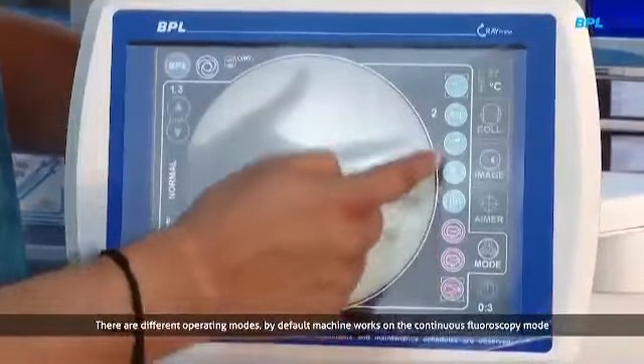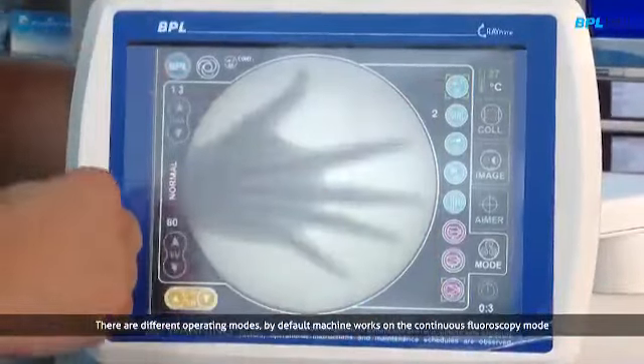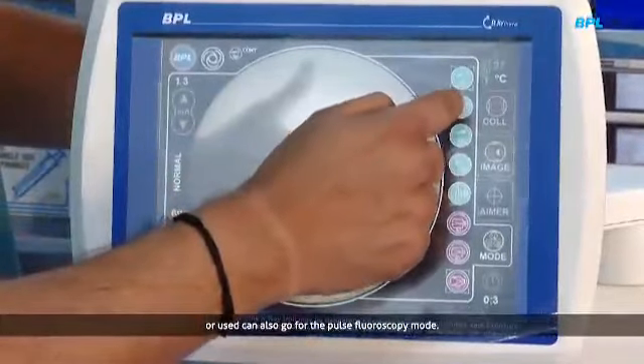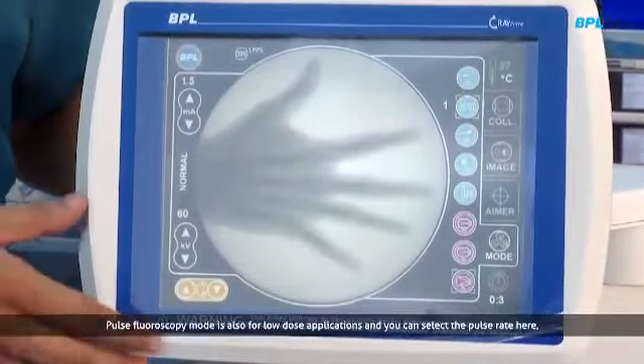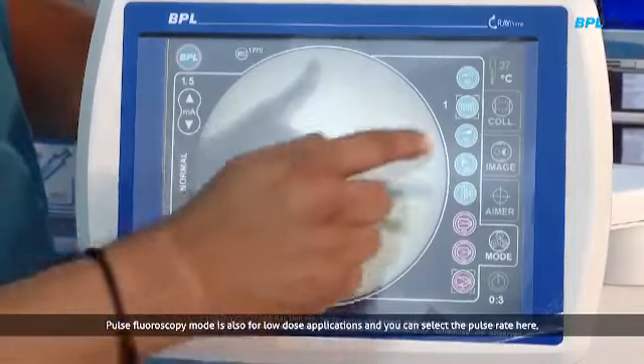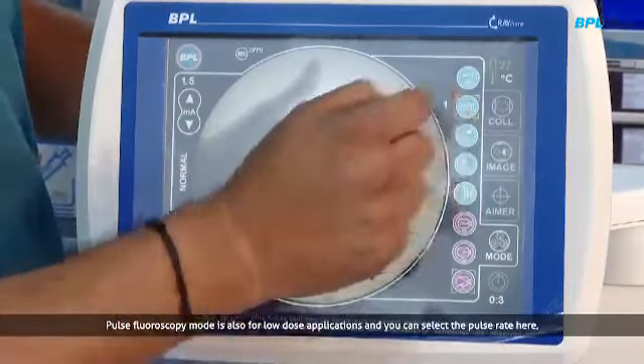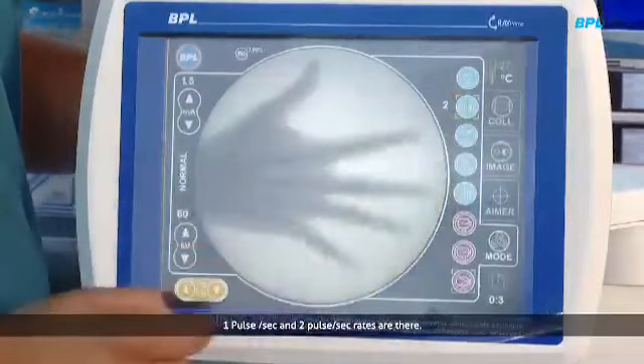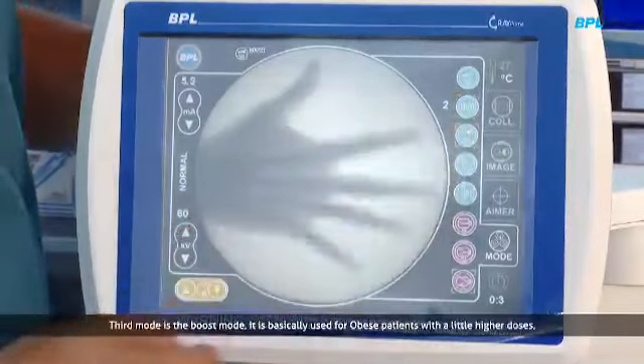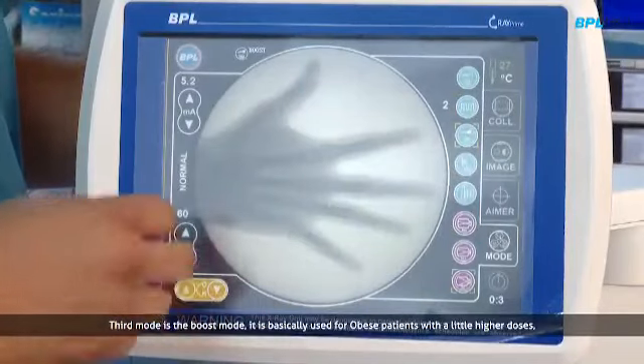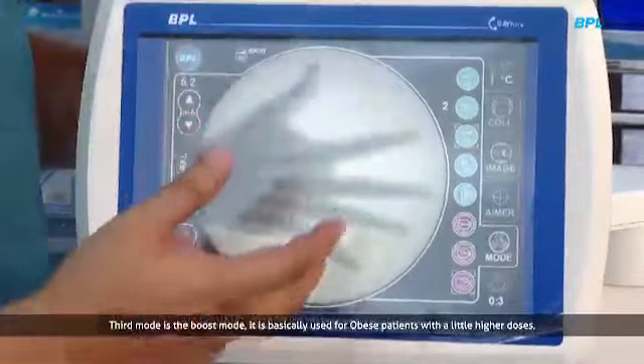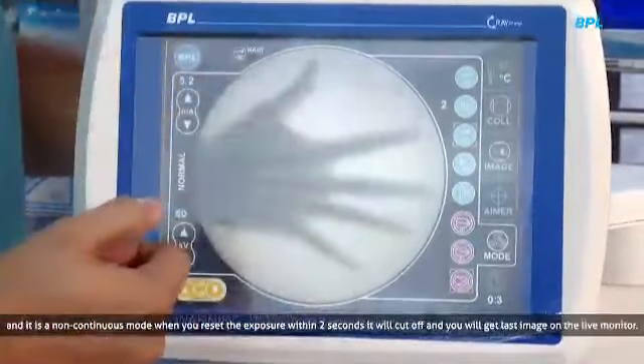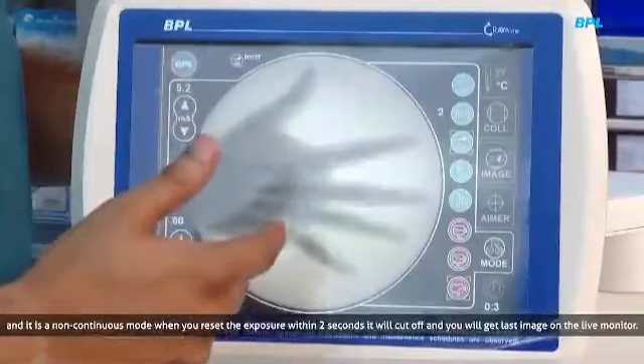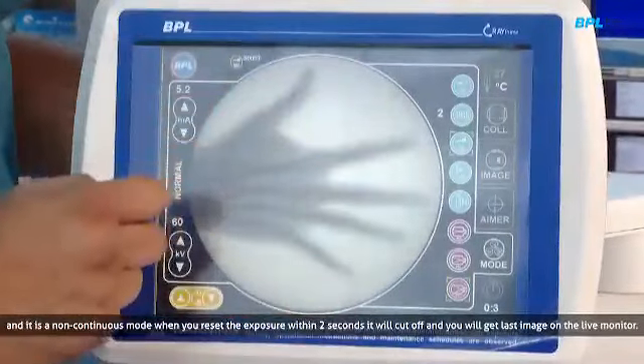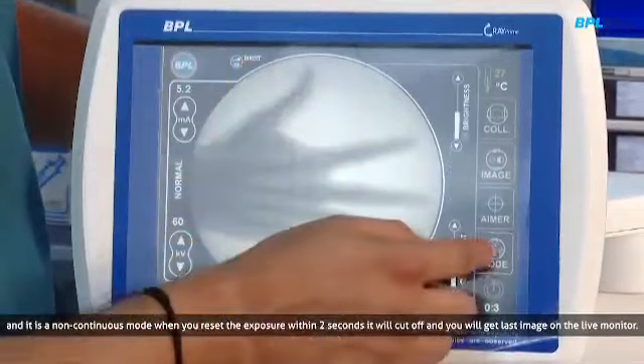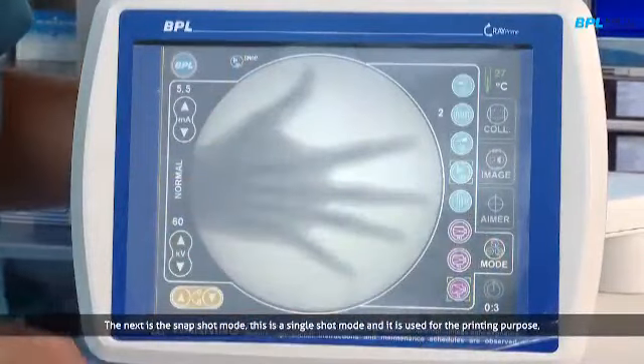There are different operating modes. By default the system operates in continuous fluoroscopy mode, or else the user can go for pulse fluoroscopy mode. Pulse fluoroscopy mode is used for low dose applications, and you can select the pulse rate from this side. So 1 pulse per second and 2 pulse per second pulse rates are there. The third mode is the boost mode. It is basically used for obese patients with little higher doses, and it is a non-continuous mode. Once you initiate the exposure, within 2 seconds it will cut off and you will get the last image held on the live monitor.